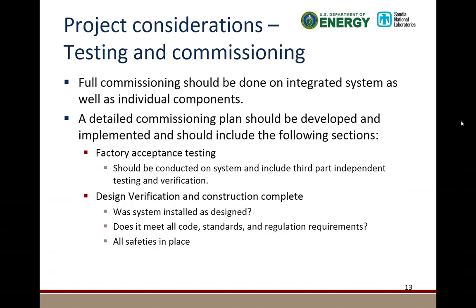And then testing and commissioning. I cannot stress this enough. Sandia through DOE is getting very, very involved with this testing and commissioning part of it to make sure that the systems are installed and they operate safely and reliably. You should do a full commissioning on the integrated system. You should have a commissioning plan talking about the factory acceptance testing, doing as much testing as you can in the factory before it hits the field. Then once it hits the field, verifying that it was installed as designed, that everything is complete. Are all your connections torqued? Did it meet all the codes, standards, and regulations? Do you have all your safeties in place?